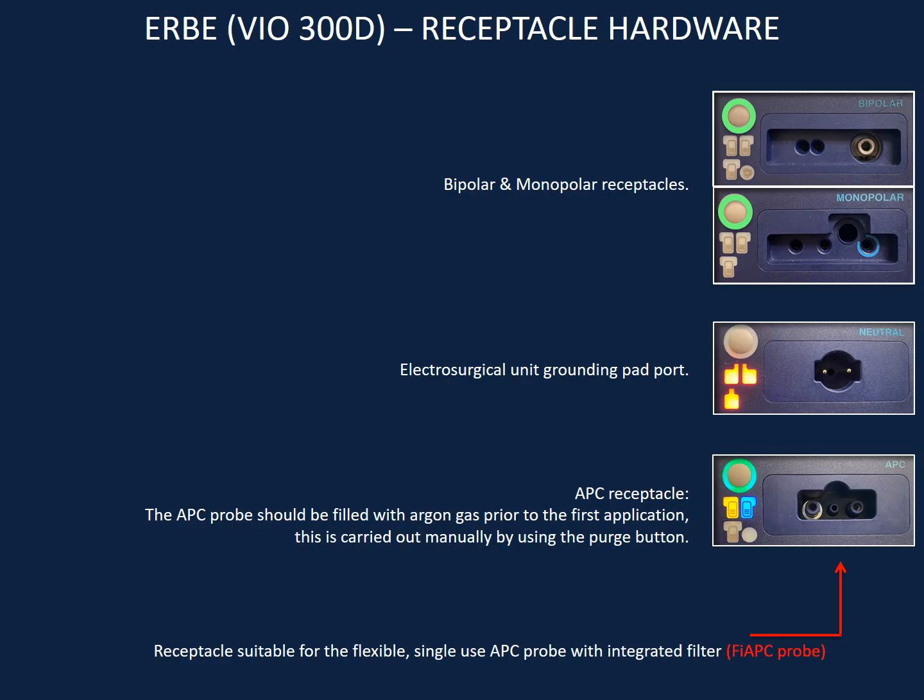This is a depiction of the ERBE unit receptacles with the different modules: bipolar, monopolar, neutral or grounding pad port, and APC receptacle. The ERBE APC probe has been designed with instrument recognition. The unit will automatically display default starting settings, which can subsequently be adjusted if deemed necessary by the physician.